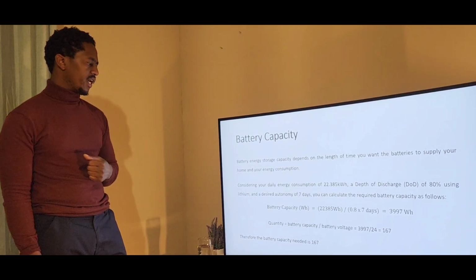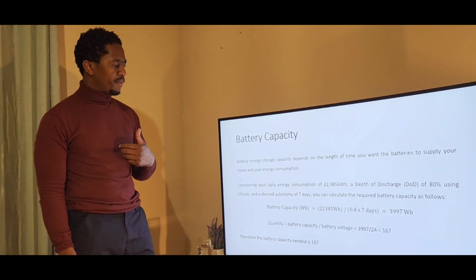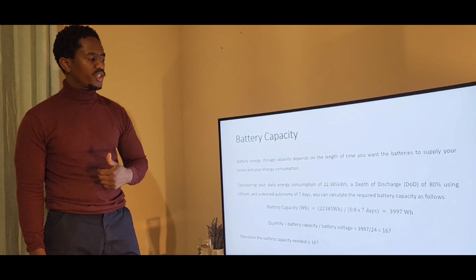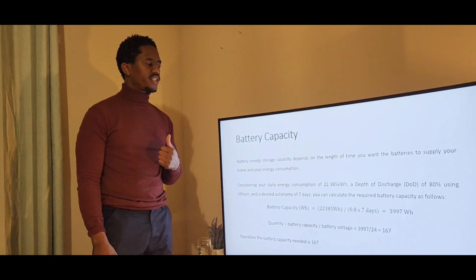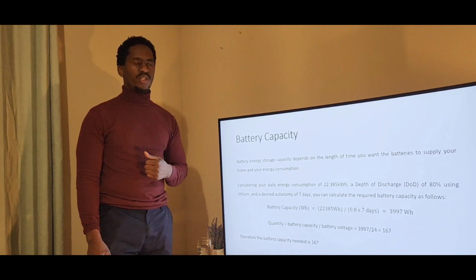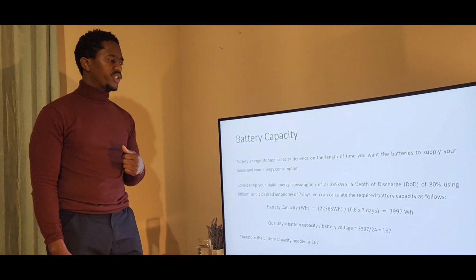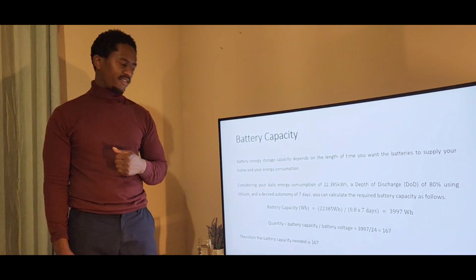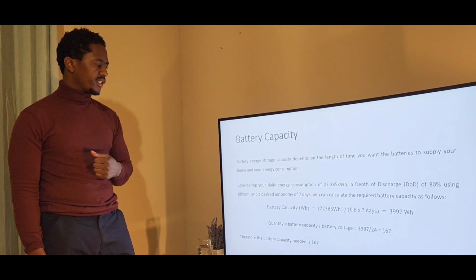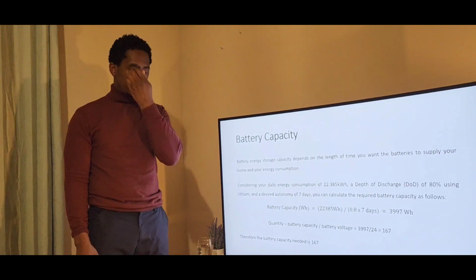3,997 watt hours. Quantity: we say the battery capacity divided by the battery voltage, which is 3,997 divided by 24 volts of the batteries, which gives us an answer of 167. Therefore, the battery capacity needed is 167.